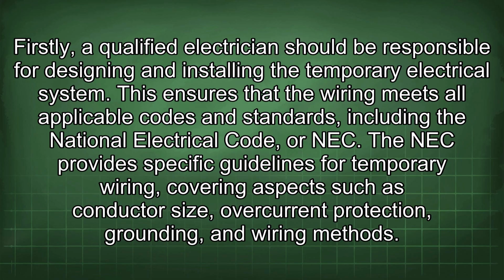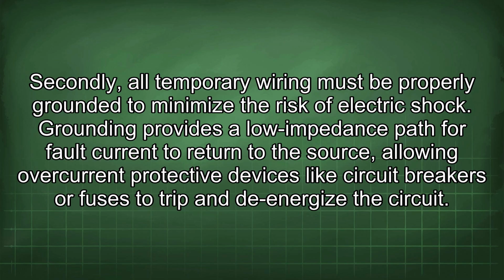Firstly, a qualified electrician should be responsible for designing and installing the temporary electrical system. This ensures that the wiring meets all applicable codes and standards, including the National Electrical Code, or NEC. The NEC provides specific guidelines for temporary wiring, covering aspects such as conductor size, overcurrent protection, grounding, and wiring methods. Secondly, all temporary wiring must be properly grounded to minimize the risk of electric shock. Grounding provides a low impedance path for fault current to return to the source, allowing overcurrent protective devices like circuit breakers or fuses to trip and de-energize the circuit.